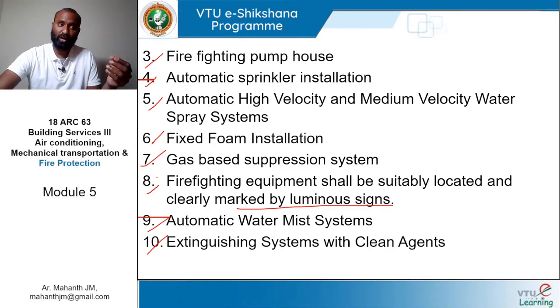this you should probably relate to your AC, specialized air conditioning systems, where you must have studied about precision. Let's not complicate it. Let's say server room requirements. We can't afford to have a sprinkler in case of a fire in a server room, right? Because the equipment is going to cost us a lot. There's no point in putting the fire off with water, because whatever damage the fire would have done, the water would do equal damage, because the entire electricity network, data network is all damaged just because they got wet. So in such cases, the systems they are going to use are not water-based systems but gas-based suppression systems.